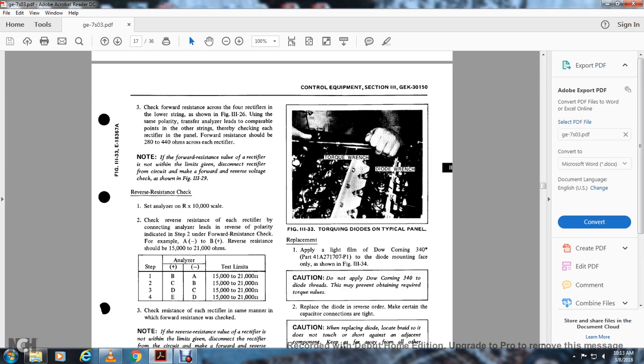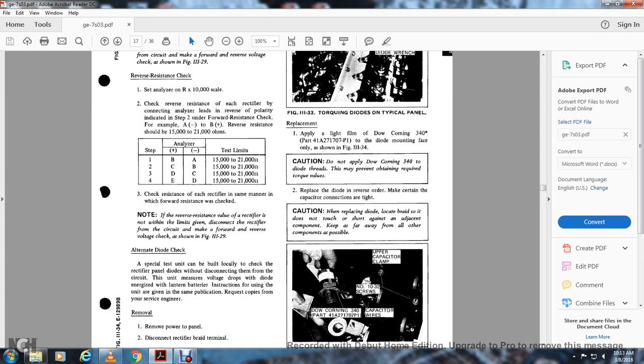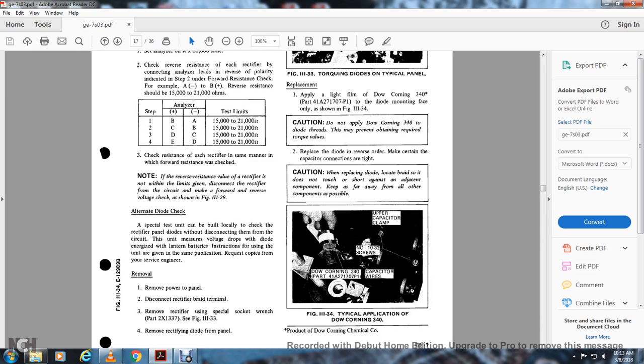Step 1 is B positive to A negative. Step 2 is C positive to B negative. Step 3 is D positive, C negative. Step 4 is E positive, D negative. Check the resistance of each rectifier in the same manner as the forward resistance was checked. Note that if the reverse resistance of a rectifier is not within the limits given, disconnect the rectifier to make the forward and reverse voltage check shown in figure 329.